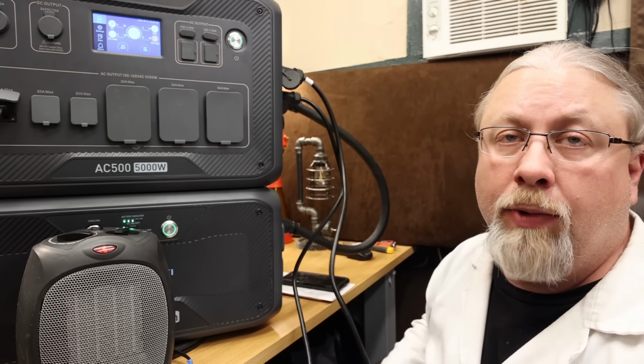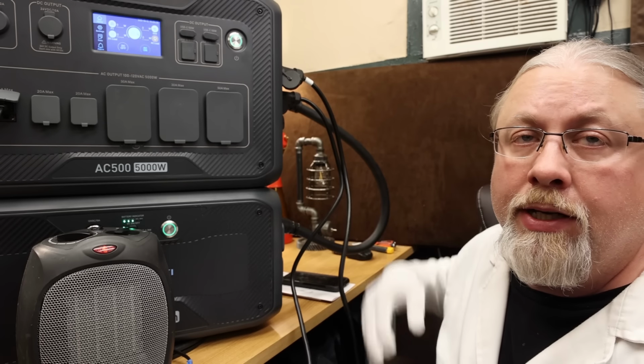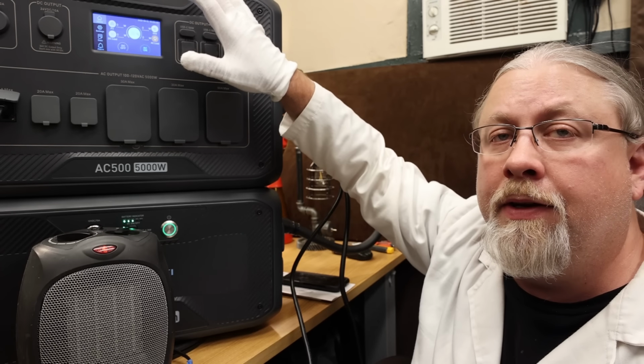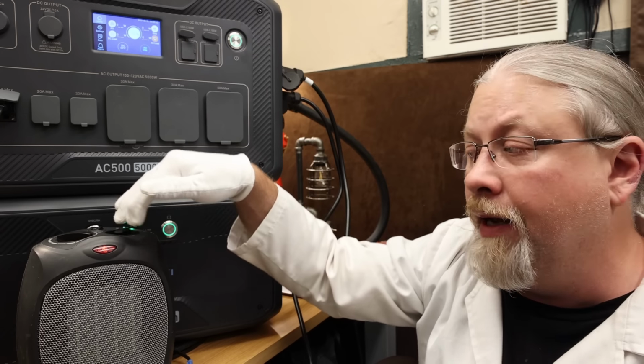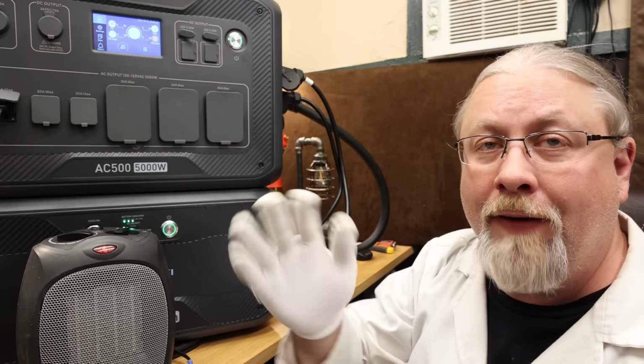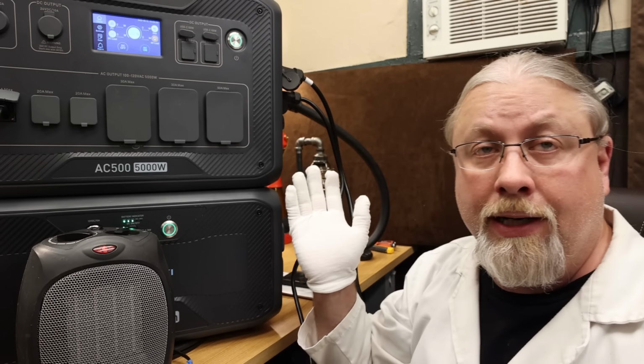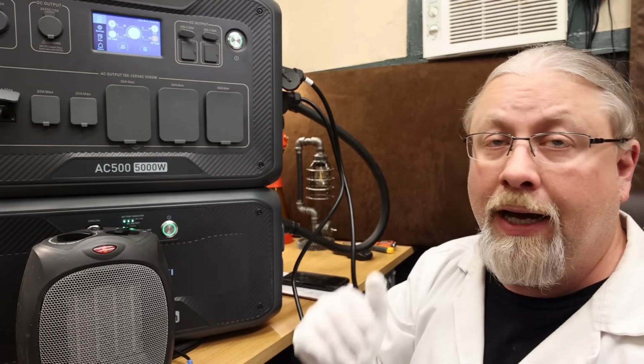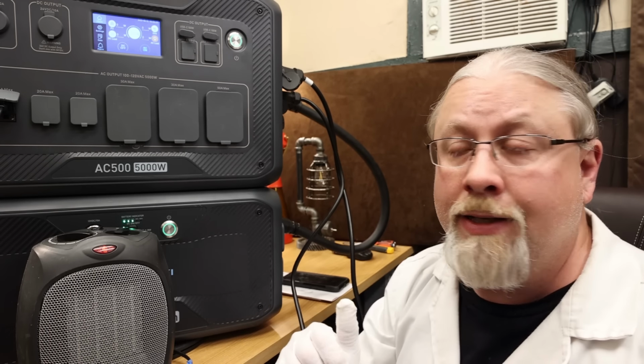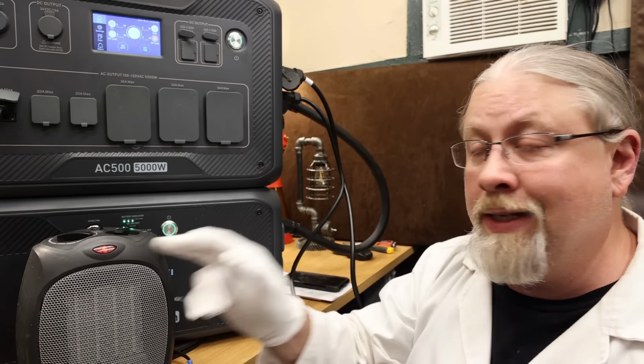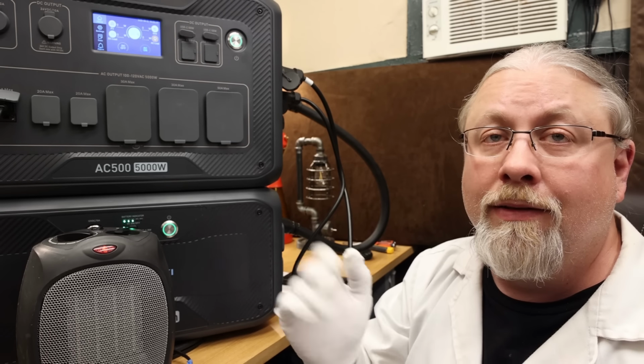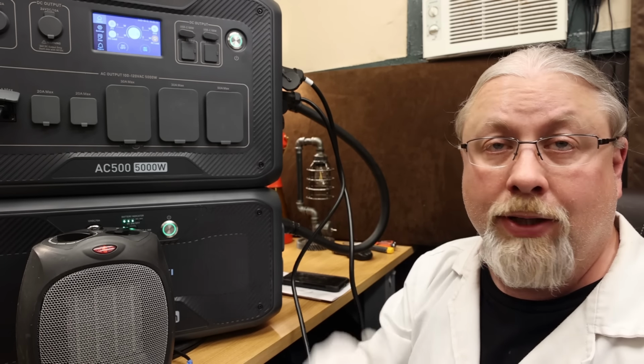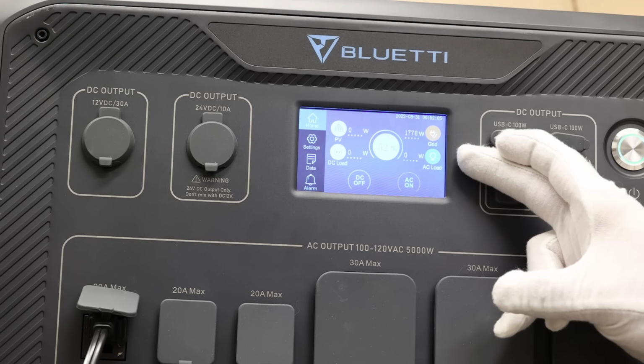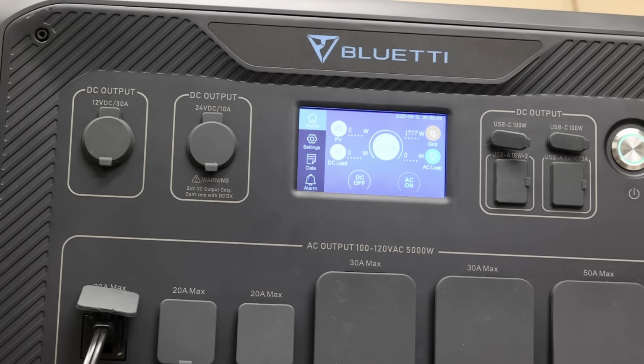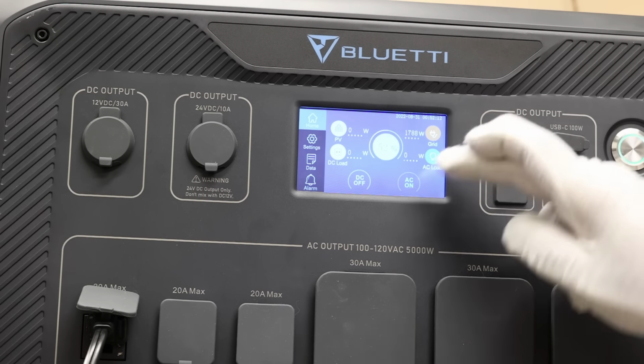We have the AC500 ready to be plugged into external power. This allows power coming in from the wall to go into the AC500, bypass the battery, and come straight out of the outlet to feed the heater. We're going to test how fast the switchover is when power goes out in your house. Is it fast enough for a computer, TV, or sensitive electronics? If the light blinks really off and on and you can see it visibly, it's probably not good for computers. But if you barely see it flicker, you could probably run a computer on it, no problem. Let's find out. That little green light bulb means we are in UPS mode. Power is coming in from the grid and going out of the outlets.